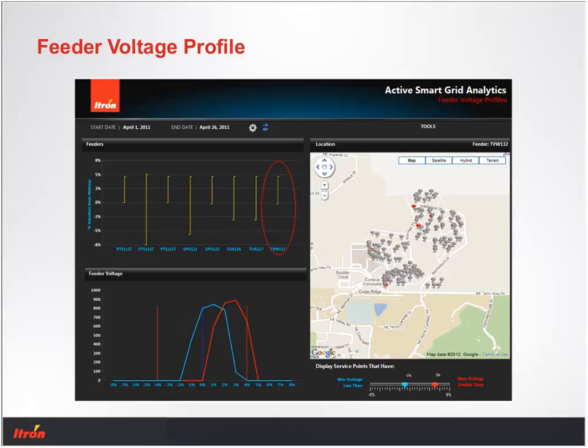Some of these feeders are varying between about nominal voltage up to about 5% above - that's good operating, right at your tariff. Some are dipping down lower, to about 3 or 4, even 5% below nominal, and those are the ones we're going to take a look at. That gives you, at a glance, a sense of how these things are operating.